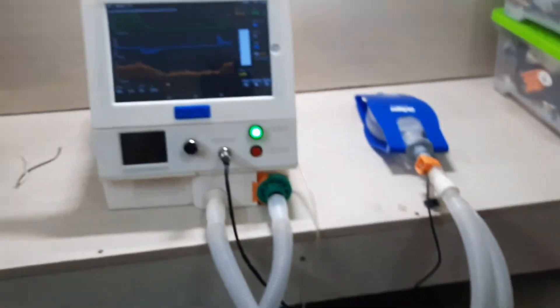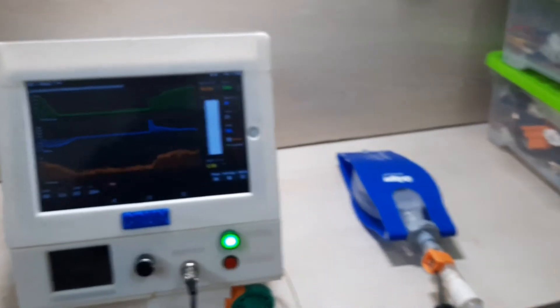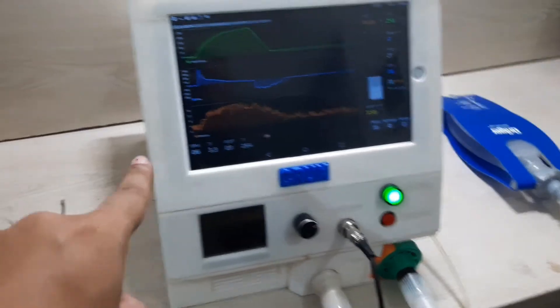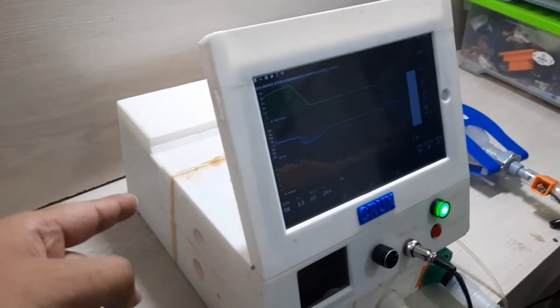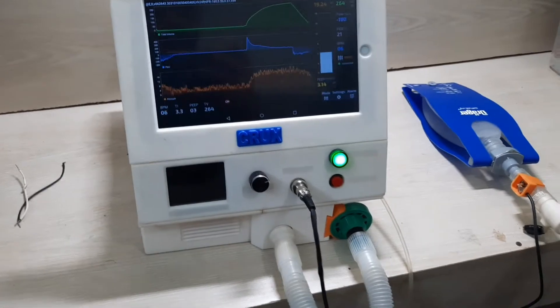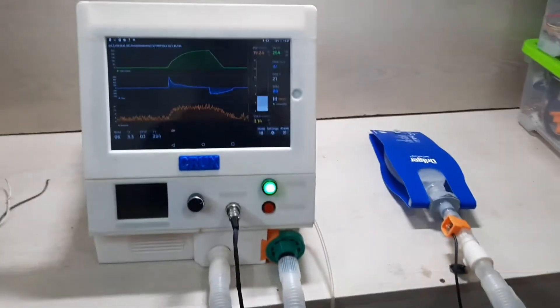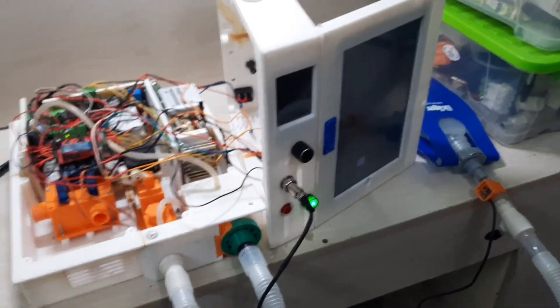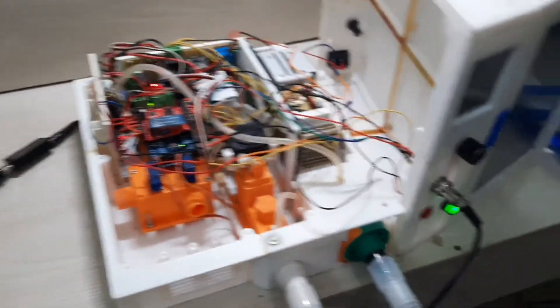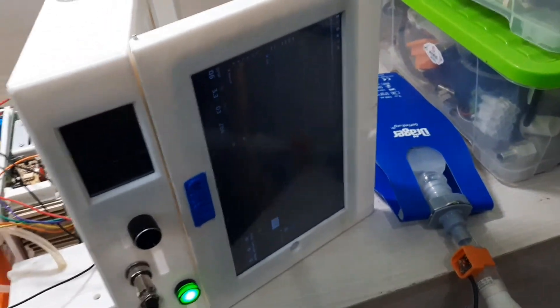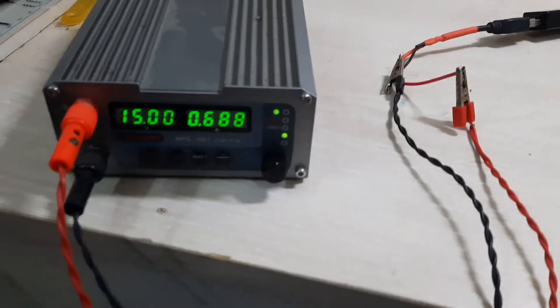Now I will show you the ventilator — the ventilator will continue ventilating while I connect the main power supply rather than the internal battery. I will disconnect the battery connection and run this ventilator completely from this power supply. I have actually opened the whole ventilator so that you can see the internal circuitry and mechanical things, and now we are running with the previous parameters. Here you can see the power supply power consumption.